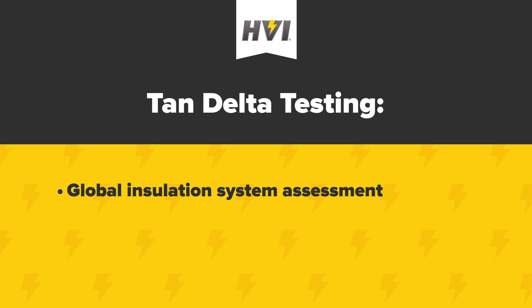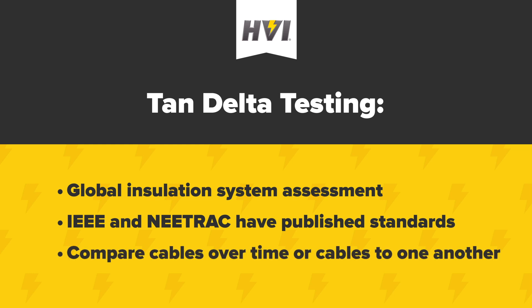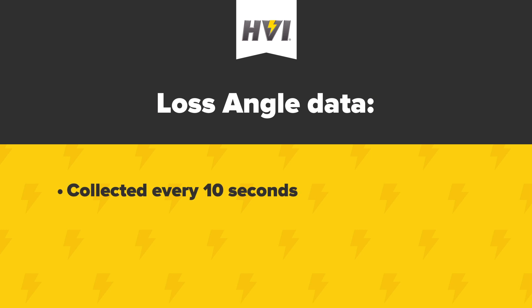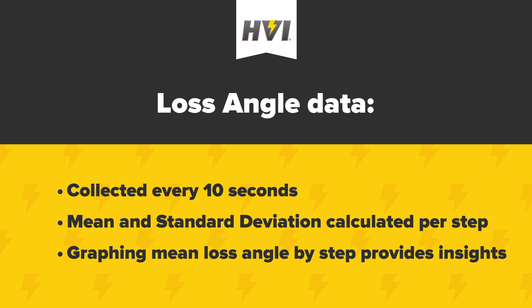Single Tan-Delta test results can be assessed using published IEEE and NEETRAC standards. But the value of Tan-Delta testing is also found by comparing the test results of a single cable over time, or comparing multiple cables to one another, in order to prioritize their maintenance and replacement. A full Tan-Delta test will take 9 minutes at 0.1 Hz, collecting data about the loss angle every 10 seconds. From those data points, the mean and standard deviation are calculated for each of the test's three steps. By graphing the mean Tan-Delta measurements for up to three steps of the test, testing professionals can easily assess the insulation integrity for the cable under test.